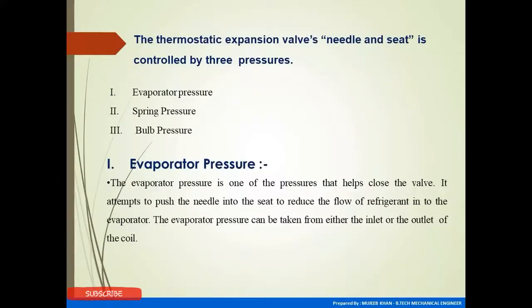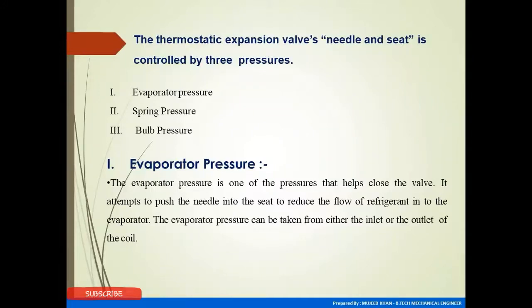The thermostatic expansion valve needle and seat are controlled by three pressures: evaporator pressure, spring pressure, and bulb pressure. The evaporator pressure is one of the pressures that helps close the valve — it attempts to push the needle into the seat to reduce the flow of refrigerant into the evaporator. The evaporator pressure can be taken from either the inlet or the outlet of the coil.